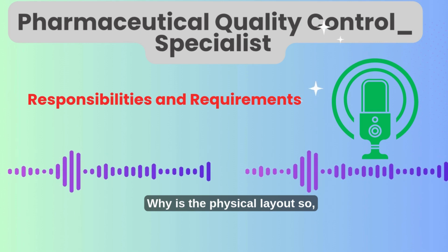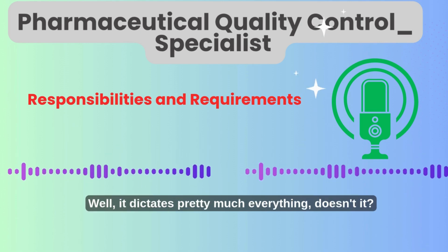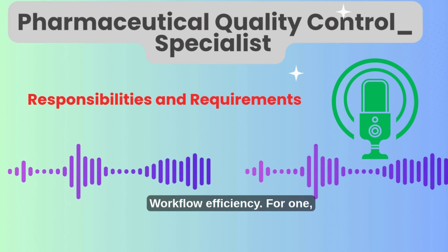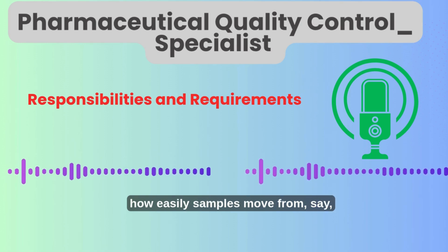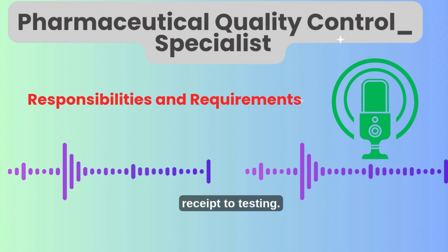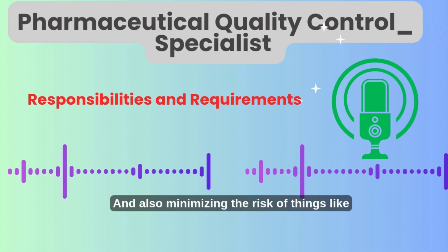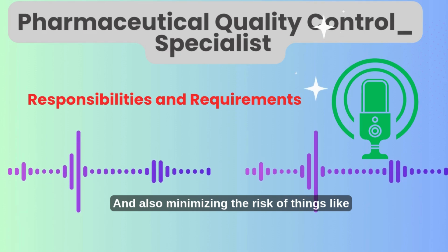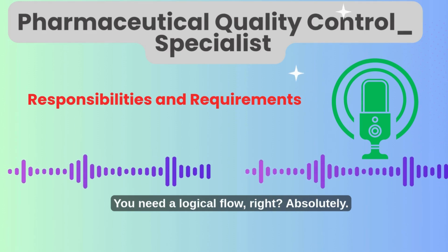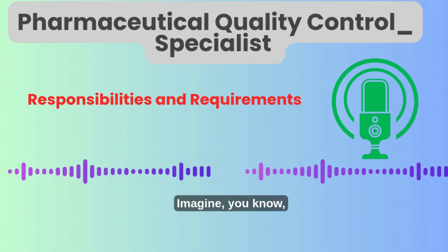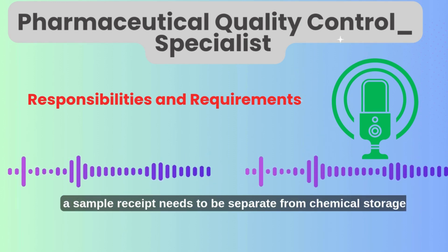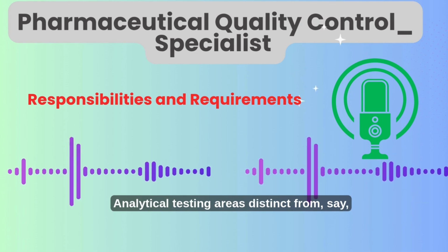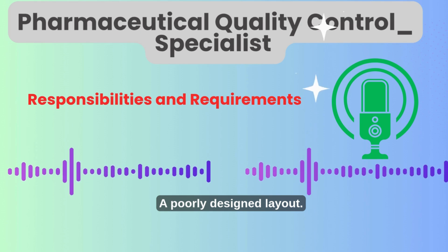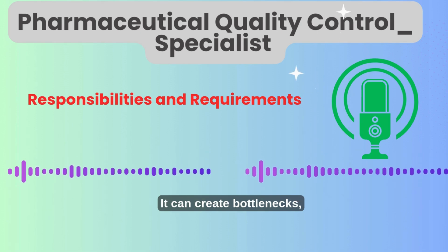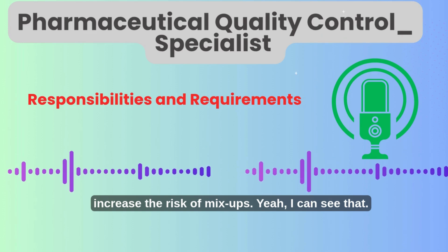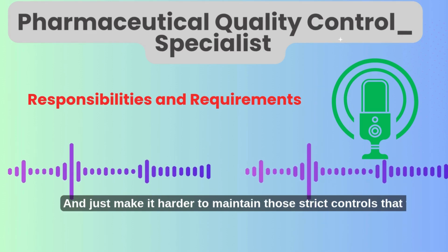Why is the physical layout so important in a QC lab? Well, it dictates pretty much everything, doesn't it? Workflow efficiency, for one, how easily samples move from, say, receipt to testing, maybe to storage, and also minimizing the risk of things like cross-contamination or just simple errors. You need a logical flow, right? Absolutely. Imagine, sample receipt needs to be separate from chemical storage areas. Analytical testing areas distinct from, say, microlabs if you have them. A poorly designed layout can create bottlenecks, increase the risk of mix-ups, and just make it harder to maintain those strict controls that the regulators demand.